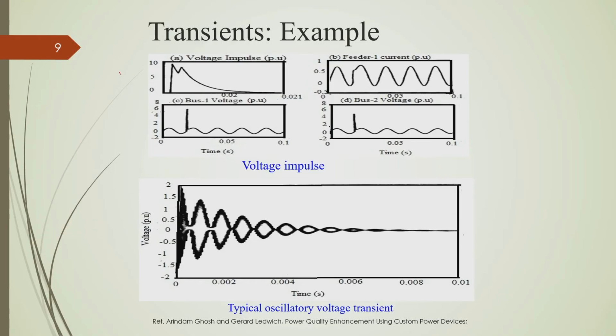Now, this is an example of a voltage impulse. You can see the impulse means a sudden increase in voltage of higher magnitude, where the nominal peak value of the voltage is 1 per unit. For a very short duration of time, the impulsive voltage magnitude may go as high as 6 to 8 per unit, that is 6 to 8 times the nominal peak voltage, which is pretty high, but it lasts for a very short period of time, in terms of microseconds or nanoseconds. So, these examples show voltage and current impulsive transients.